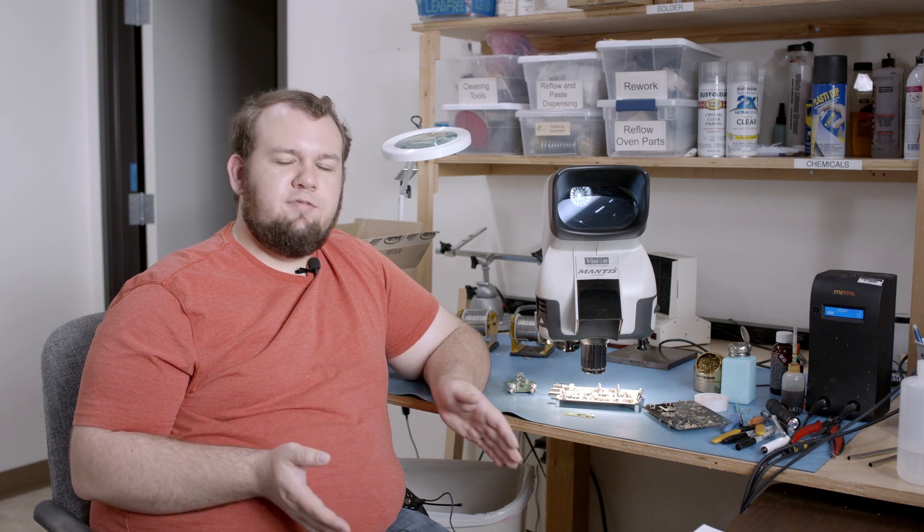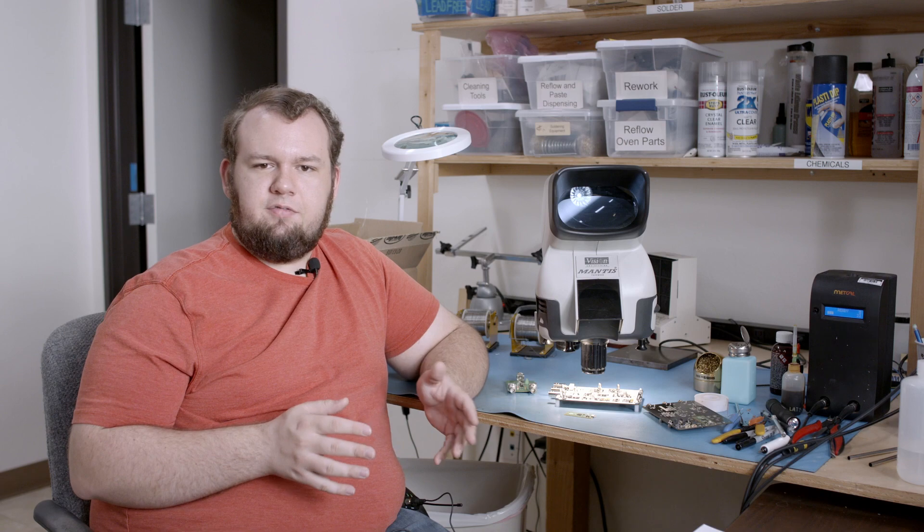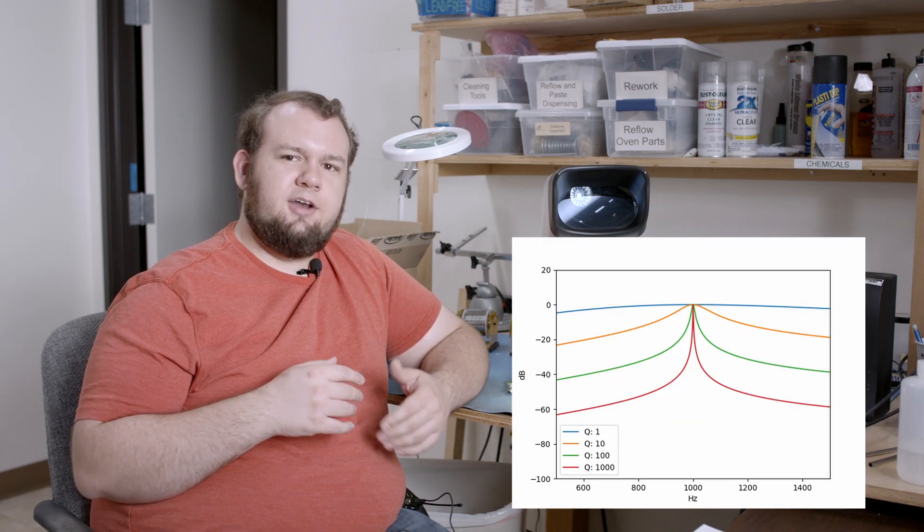A lock-in amplifier is an instrument that cuts out all the noise, leaving behind just the signal. It does this by forming an impossibly narrow bandpass filter. The narrowness of a filter is defined as its quality factor, with conventional filters typically capping out around a quality factor of 100.